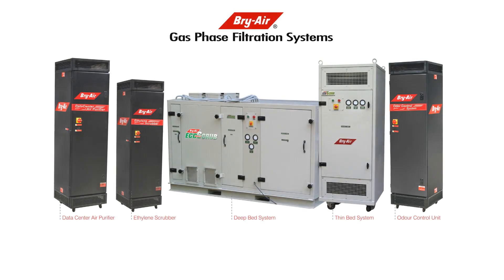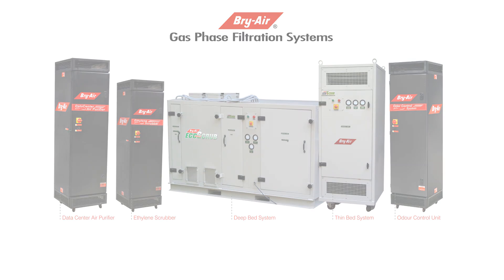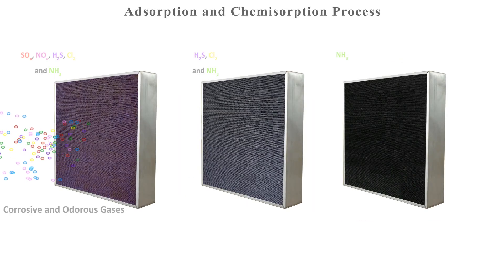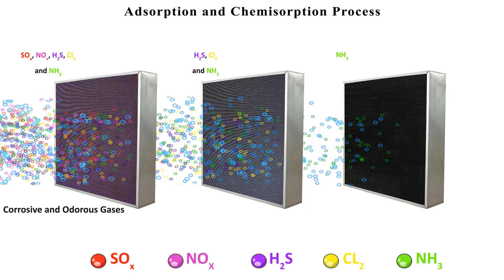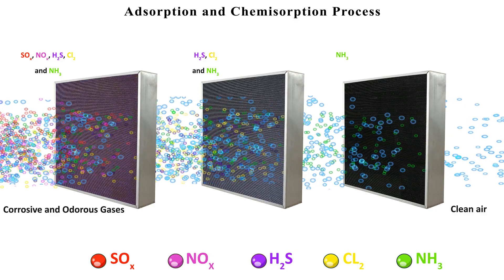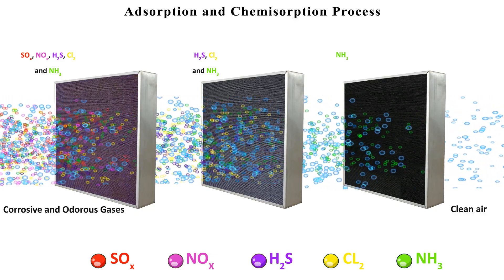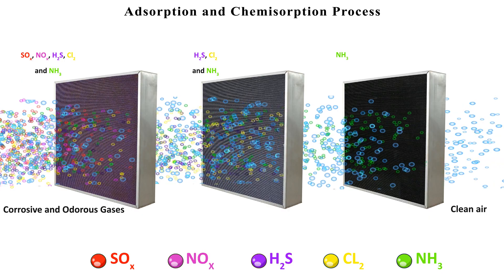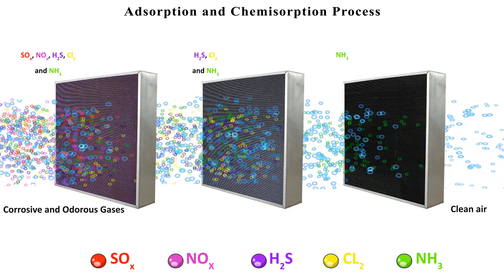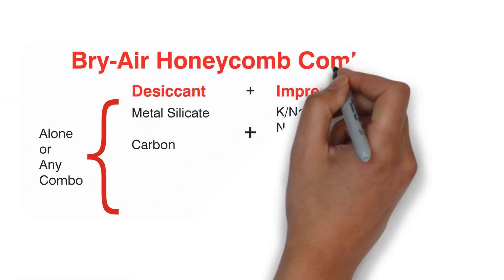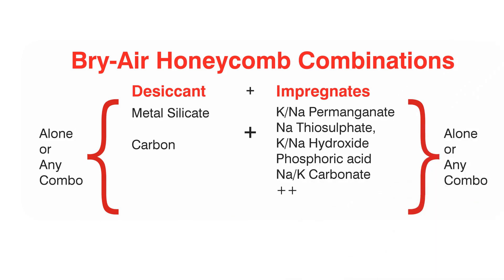The Bry-Air gas phase filtration system is an ideal and the most cost-effective solution to all these problems. The process of purification is simple. The contaminated air stream first passes through the required chemical media beds, which chemically neutralize the contaminant gas molecules and convert them to non-toxic, non-hazardous materials through a process called chemisorption. The chemical media can be activated carbon and/or activated alumina impregnated with proprietary chemicals, used alone or in combination depending upon the types and concentrations of the impurities present in the air stream.